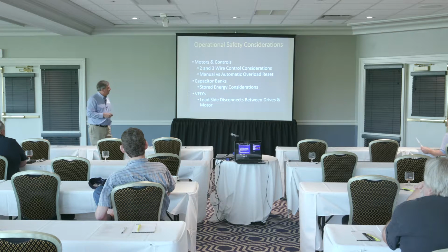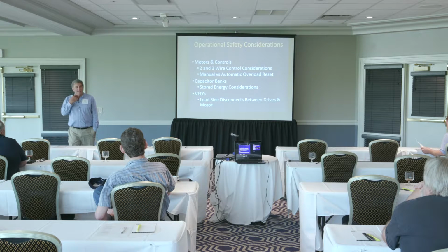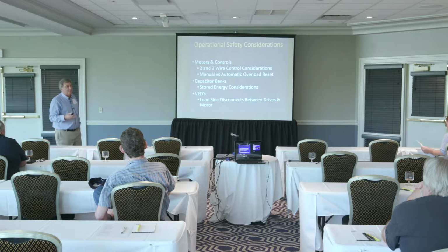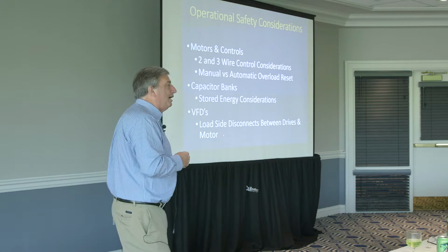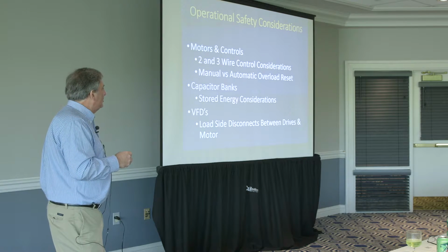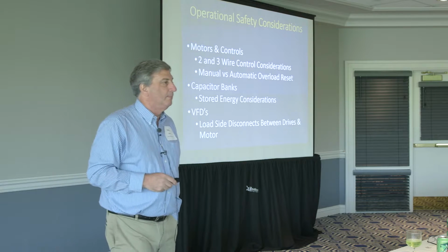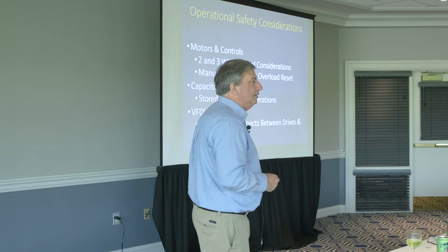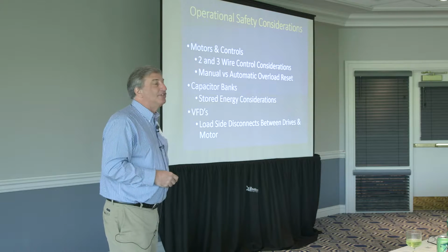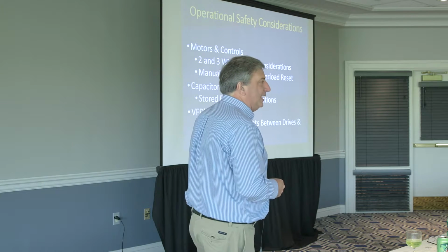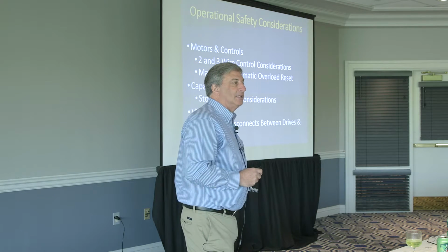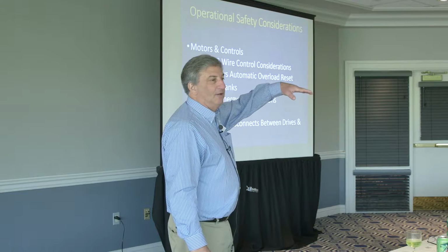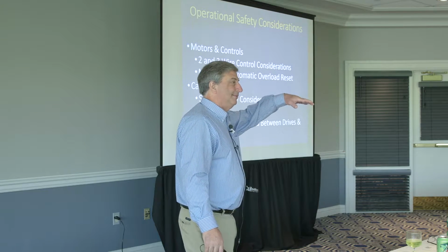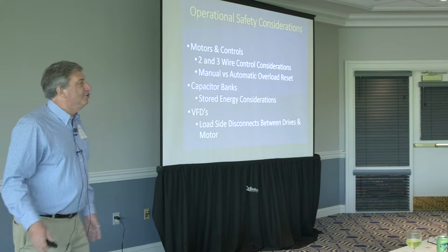And then VFDs, kind of a strange one, and I thought when people started asking me, why in the world do you want to do that? And then they gave me some reasons that made sense. What is my concern and why have some people been hurt when people put a load side disconnect between the VFD and the motor? What do I have to think about now in terms of safety procedures, special training, by having a disconnect between the VFD and the motor, and somebody walking up, instead of turning the VFD off, opening that disconnect to disconnect the motor while the VFD is still running? And if you've ever seen any videos on YouTube or anything else, bad things happen when I do that. Number of things the drive can do.